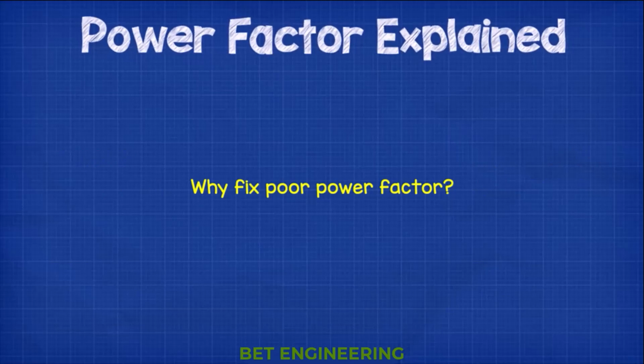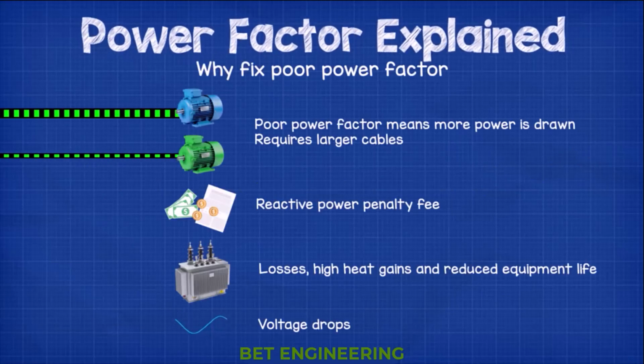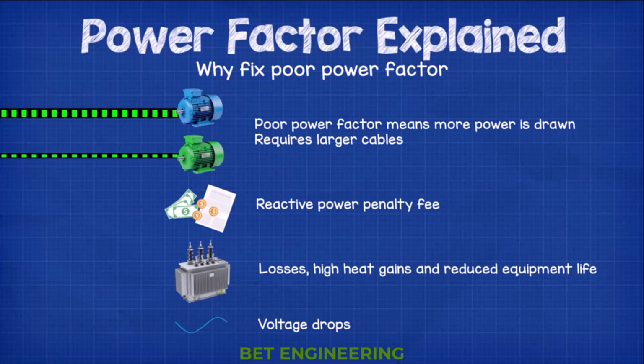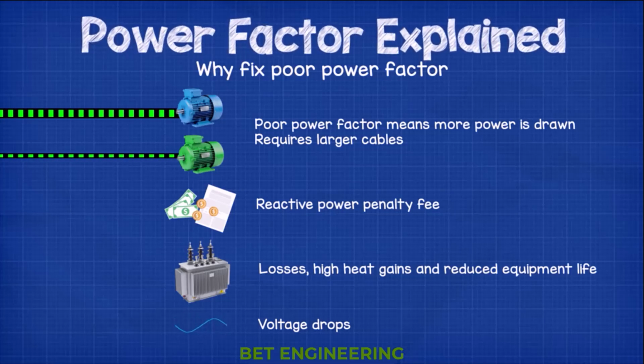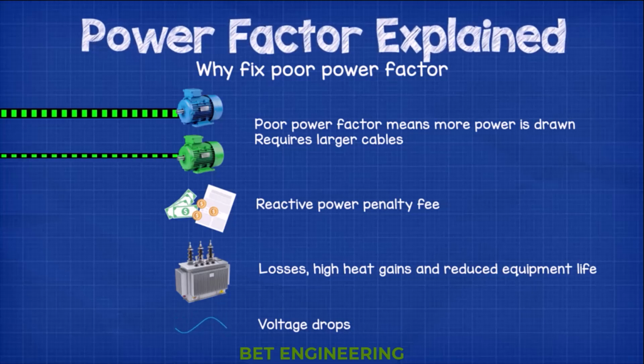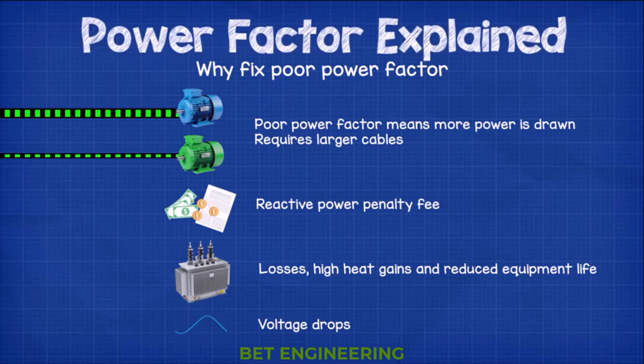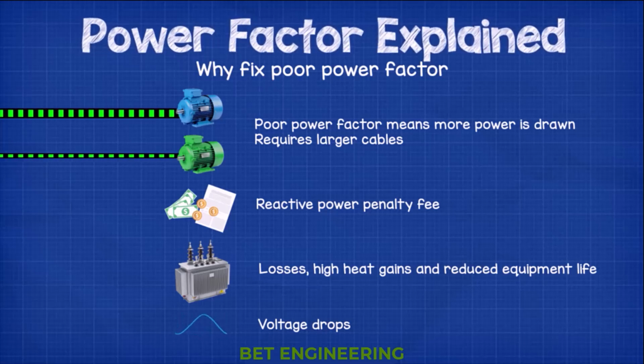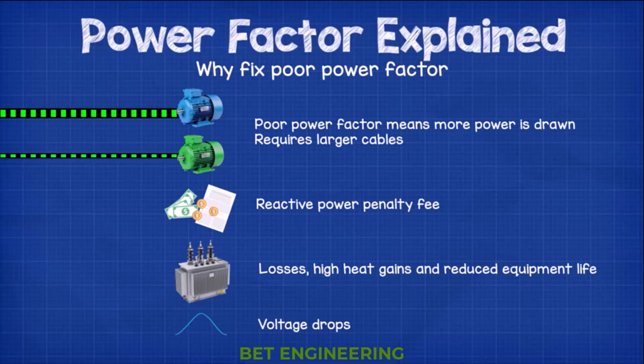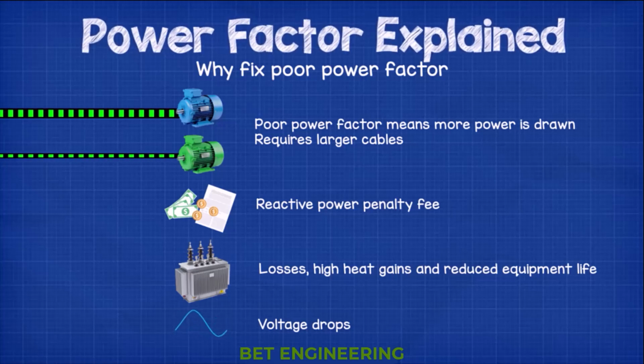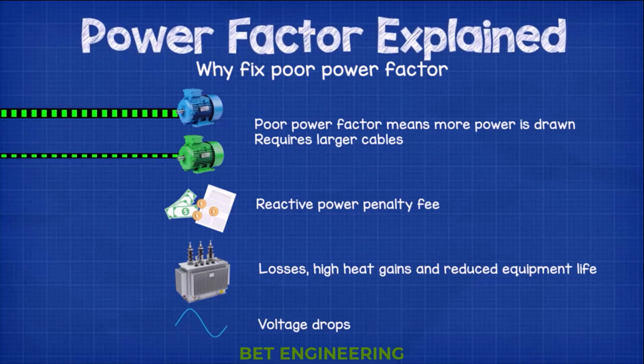So why should we fix poor power factor? Poor power factor means you need to draw more power from the electricity network to do the same amount of work. Therefore, the cables need to be larger, so the installation is going to cost more money. If the power factor becomes too low, then the electricity supplier might charge you a penalty fee or a reactive power charge. Poor power factor can also reduce the life expectancy of equipment in extreme scenarios.